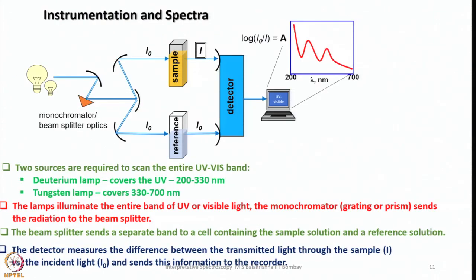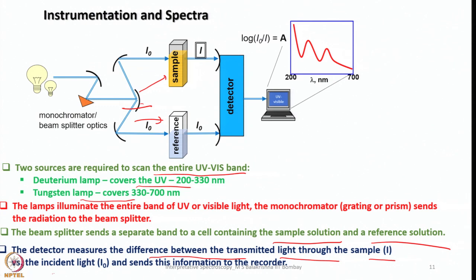This is how a typical instrument looks. Two sources are required to scan the entire UV-visible band: the deuterium lamp covers 200 to 300 nanometers (UV region) and the tungsten lamp covers 300 to 700 nanometers (visible region). The lamp illuminates the entire band; the monochromator sends radiation to a beam splitter, which sends a separate band to a cell containing sample solution and a reference solution. The detector measures the difference between the transmitted light through the sample versus the incident light and sends this information to the recorder, giving us the spectrum.